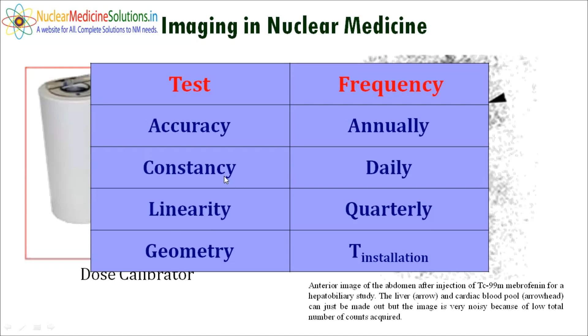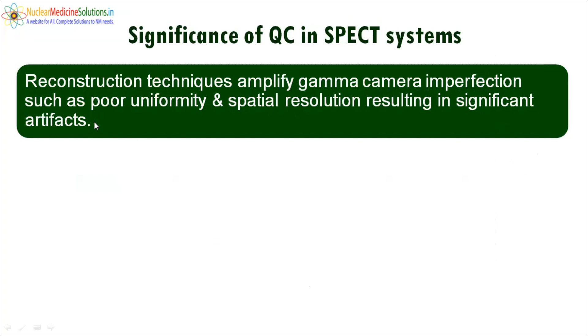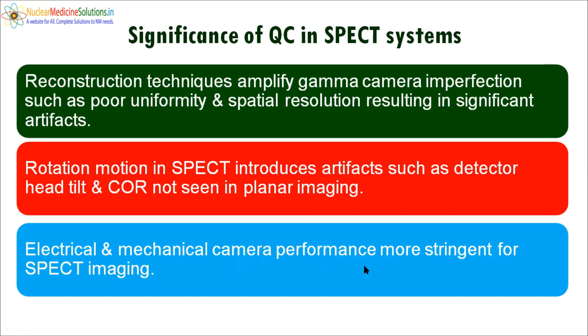Reconstruction techniques amplify gamma camera imperfections, such as poor uniformity and spatial resolution, which results in significant artifacts in the image. Rotation motion in SPECT introduces artifacts, such as detector head tilt and COR errors, which are not seen in planar imaging. Electrical and mechanical camera performance is also more stringent for SPECT imaging.